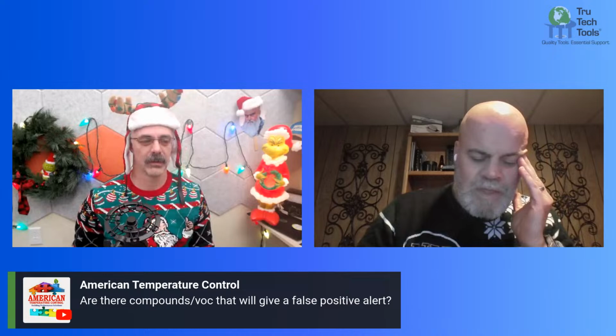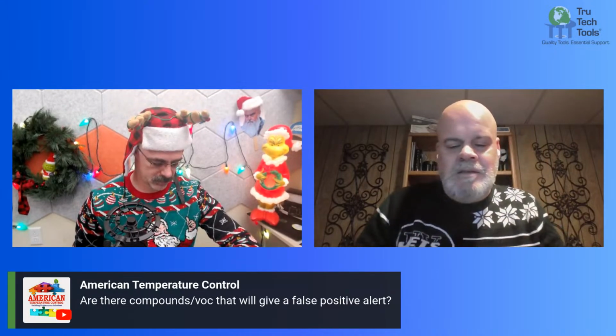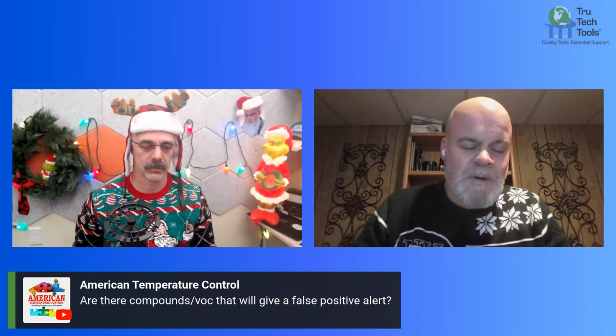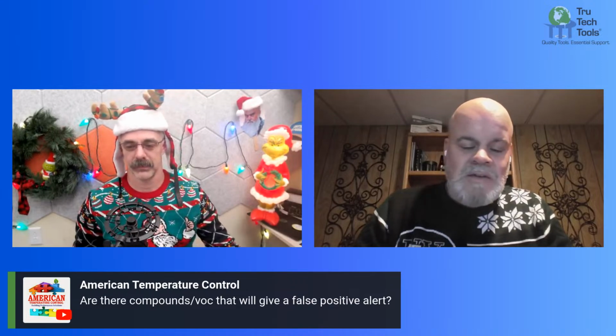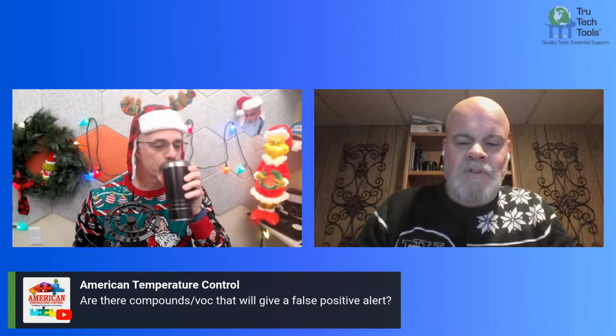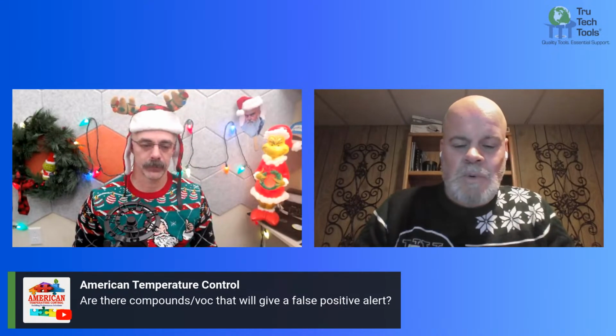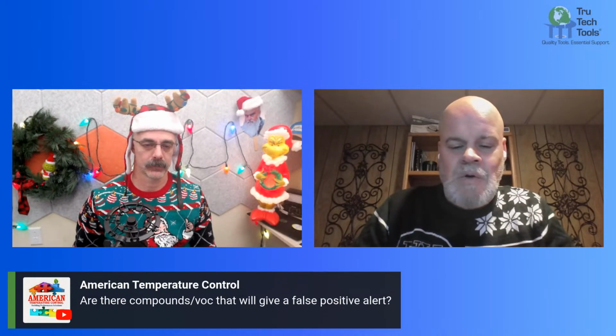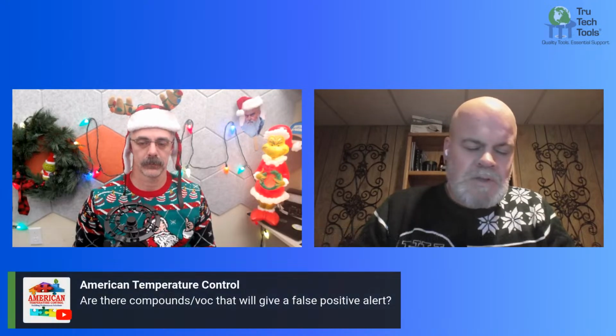So a false positive can happen if you're using a combustion analyzer that's antiquated or just a lesser quality investment. If your CO sensor doesn't have a NOx filter on it, you can get an inflated carbon monoxide reading. What a NOx filter does is filter out the crosstalk that NOx can create. For example, if I'm reading 60 ppm of CO with an analyzer without a NOx filter, the actual level could be, just as an average, between 30 and 37 ppm. That can make the difference between shutting something down prematurely or not. So I strongly recommend using analyzers with NOx filtration on the CO sensor, not just from us but from many manufacturers. It's a very important piece of kit to have in your arsenal.